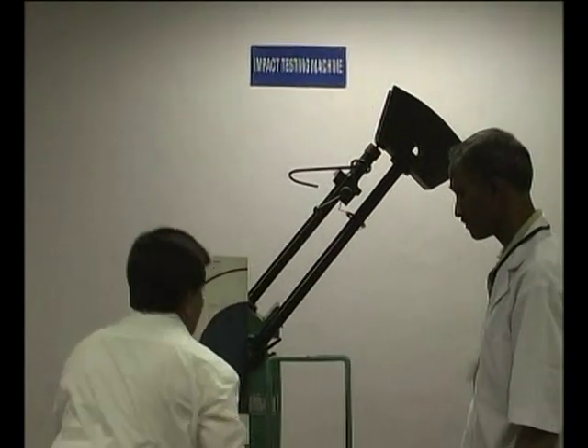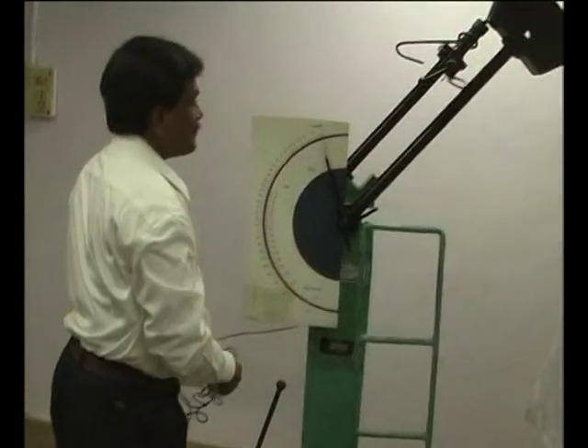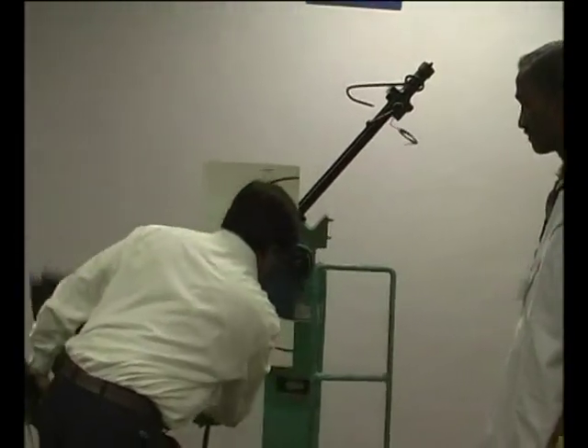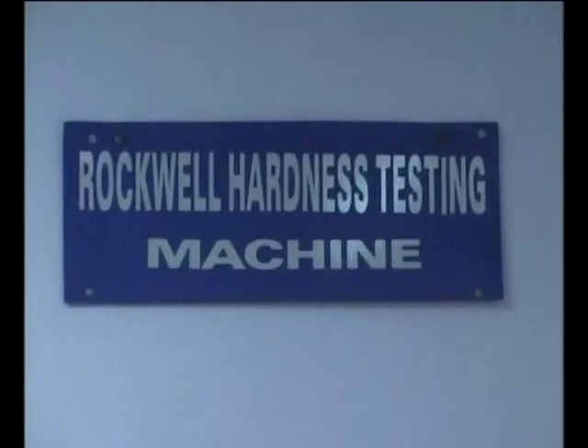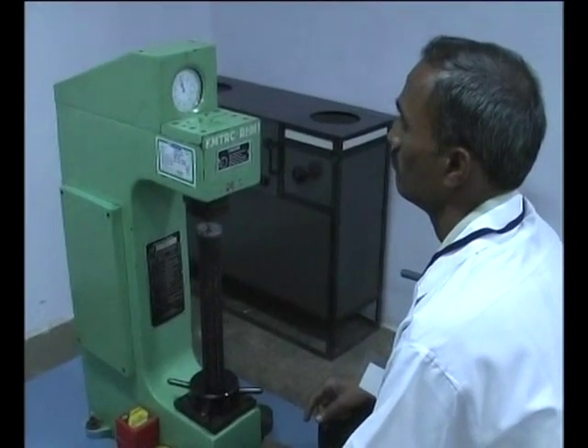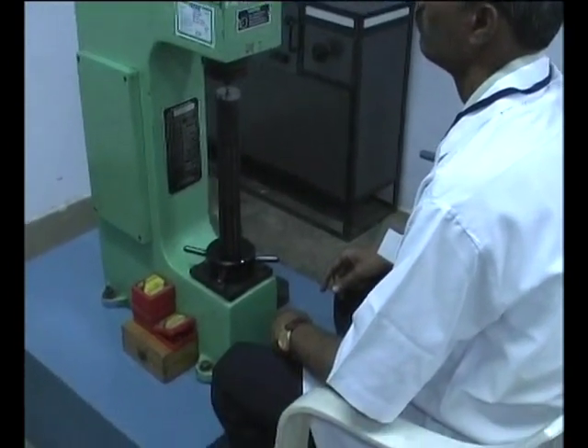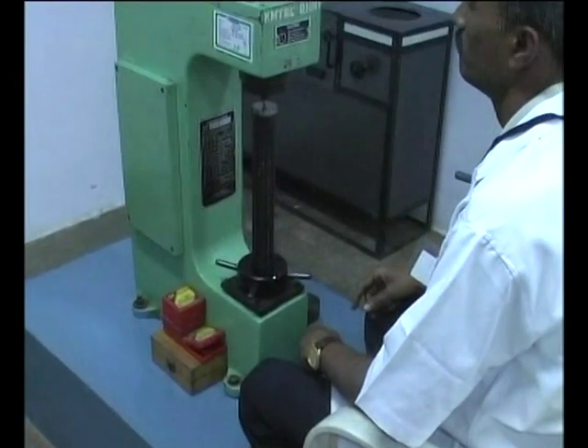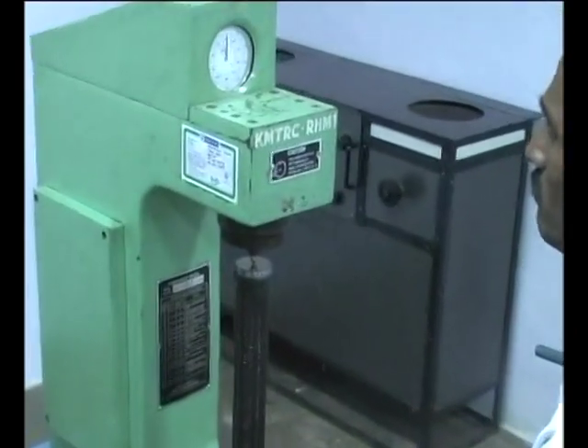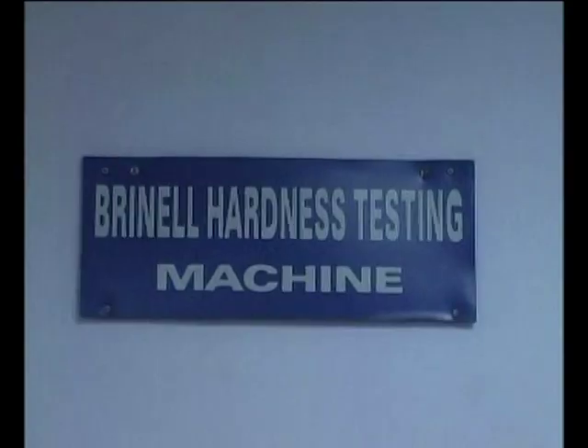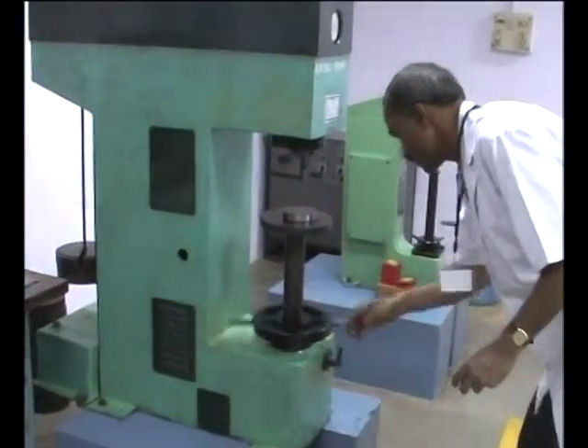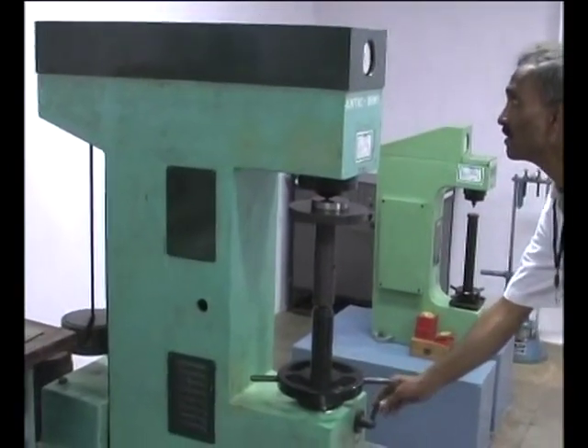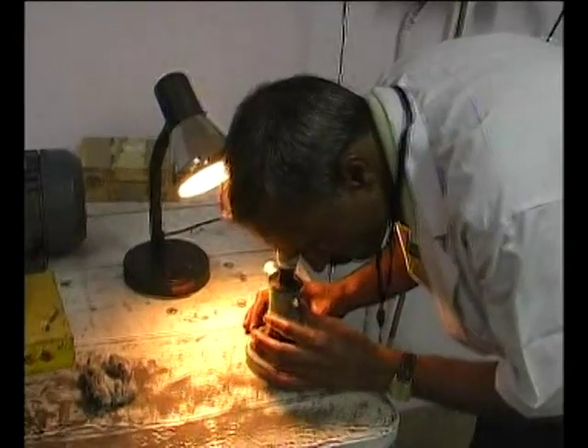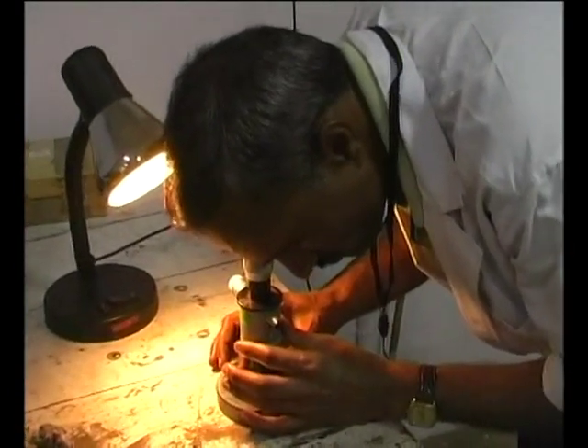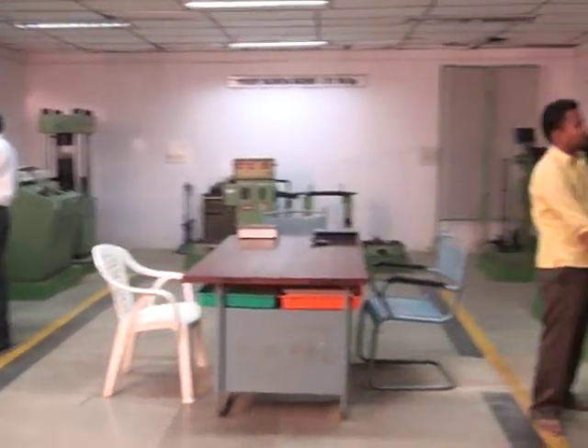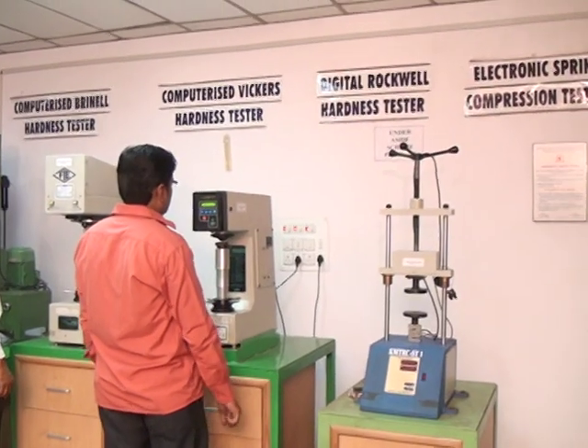Impact testing machine. Impact tests for Charpy and Izod can be done here at room temperature and -50 centigrade. Rockwell hardness testing machine. This instrument is meant to test the hardness of metals and gives the hardness on C scale and B scale. Brinell hardness testing machine. Brinell hardness number can be examined by this machine for non-ferrous metal. These machines are calibrated periodically by reputed NABL approved agencies.